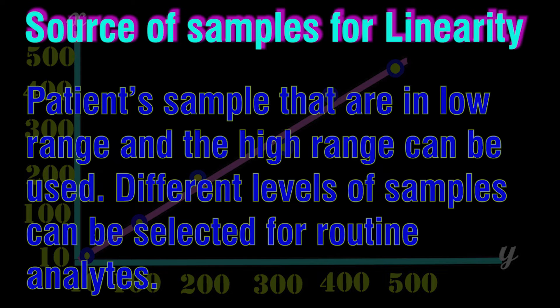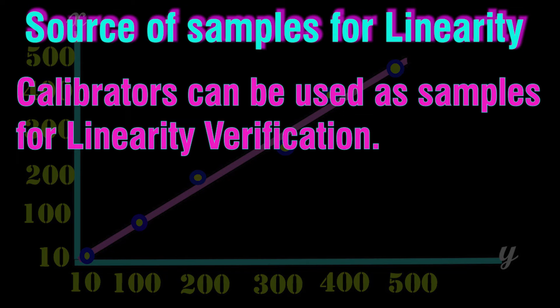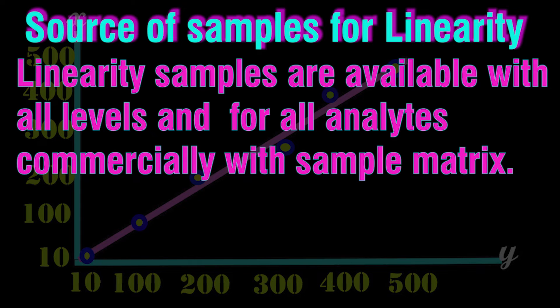Sample source materials and acceptability criteria are determined by the lab director. Patient samples can be used; high-level samples can be preserved and used with different dilutions for different concentrations. Standard reference materials can be used for calibration verification. Calibrators can be used, and commercially available kits are used for linearity or calibration verification. The basic requirement is that materials must cover the minimum and maximum reportable range and analytical measurable range, and samples can be diluted at any intervals.